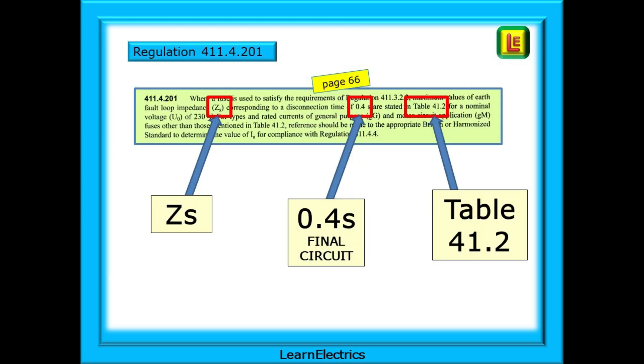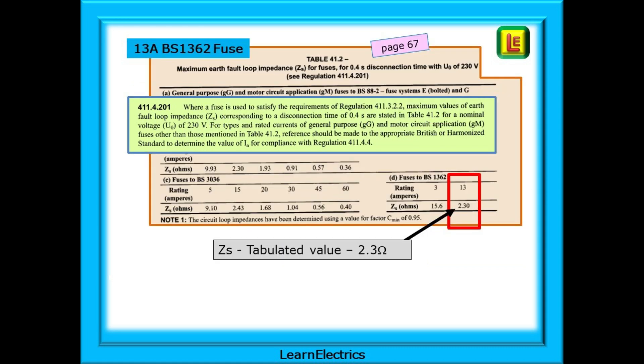Regulation 411.4.201 on page 66 of the Brown Amendment 2 regs book gives us the information that we need. The ZS for final circuits protected by fuses requiring a 0.4 second disconnection time will be found in table 41.2, and we will find this table on page 67. Here is table 41.2 and shown in the red box is the maximum tabulated ZS value for a 13 amp BS 1362 fuse. This is 2.3 ohms and will need to be converted to a maximum permitted measured value to compare with our on-site readings with a test meter.